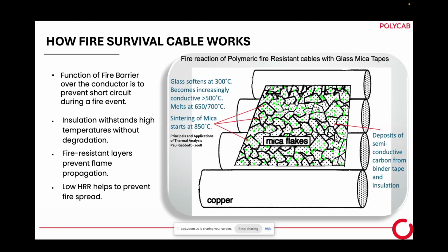One is called phlogopite, which has a little bit low insulation resistance but very high temperature withstanding capacity. It can go to 1100 degrees temperature, but the insulation resistance is a little bit low. Another is called muscovite. Muscovite has very high insulation resistance, but it can withstand temperature up to 1050 degrees. Muscovite is costly, phlogopite is less costly, and availability is very good. So whatever we do, we take muscovite mica, because the insulation resistance is very high. Though it is costly, it gives a better result.